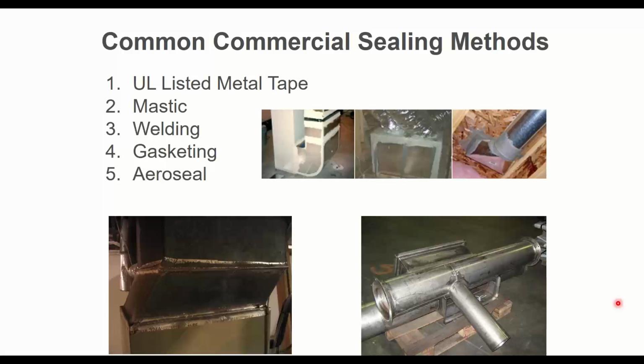If you're sucking air in from all the wrong places on the return duct, right, basements, crawl spaces, attic cavities, wall shafts, dirty areas, if your return duct is leaky, you suck that crap in, and then you distribute that crap everywhere else. Crap is a technical term. So you decide to make this improvement happen. These are the ways you can do it. You can use the UL listed tape, right? That's easy. Pretty much anybody can do that. The challenge there is physically getting to all the places that have the duct leakage. Some spots it's easy, some spots it's pretty hard.